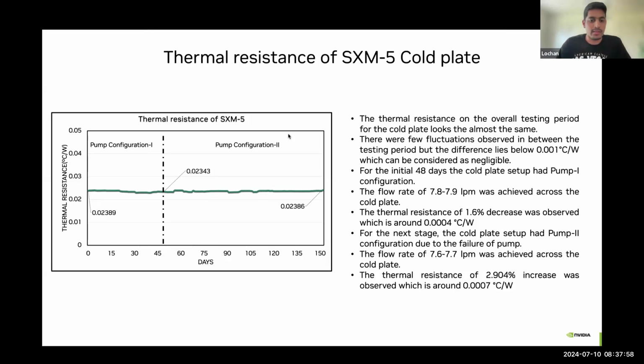And from the thermal resistance point of view, we see that there is not much effect of higher flow rates on the cold plate over a long period of time. We can even continue working at the same high flow rates on the cold plate for an even longer period of time without any damage to the cold plate.